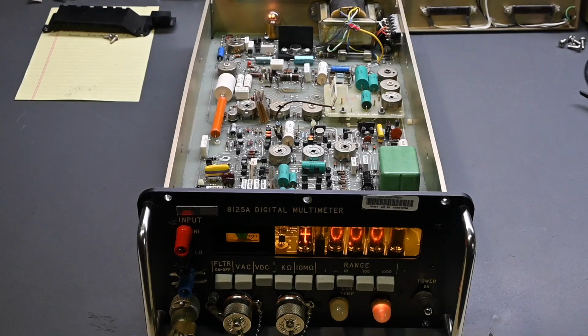So I wanted to do a quick test on the instrument just to make sure everything was looking okay, and I noticed right away that the ring counter circuit was still unstable, just like it was before and everything that I showed you in that part 1 video. So touching that test link jumper stabilizes the ring counter, and that hadn't changed. So I did that, the ring counter became very stable, and I put in some DC voltage, AC voltage, a couple of test resistors, and everything was looking very, very good at that point.